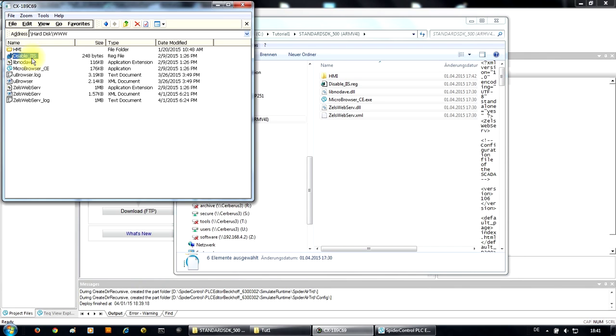This will disable the IIS web server, which is still blocking the port 80, and the script will move the IIS web server away in order to allow our web server to run here. The web server is started by calling this MicroBrowser CE launcher application. This application will be called automatically by the Beckhoff Windows CE image, so you do not have to worry about the automatic start at power up.